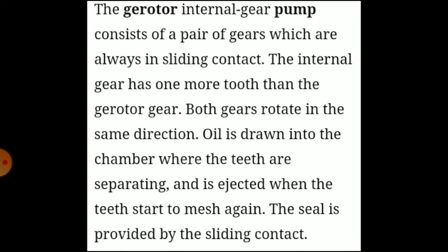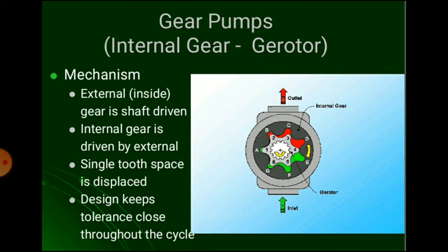Now the working: when the inner element rotates, the pockets go on increasing in size due to motion. These increasing pockets create suction and suck the oil into the suction chamber. Whereas the pockets on the pressure side decrease in size as a result of motion and force the fluid to discharge.